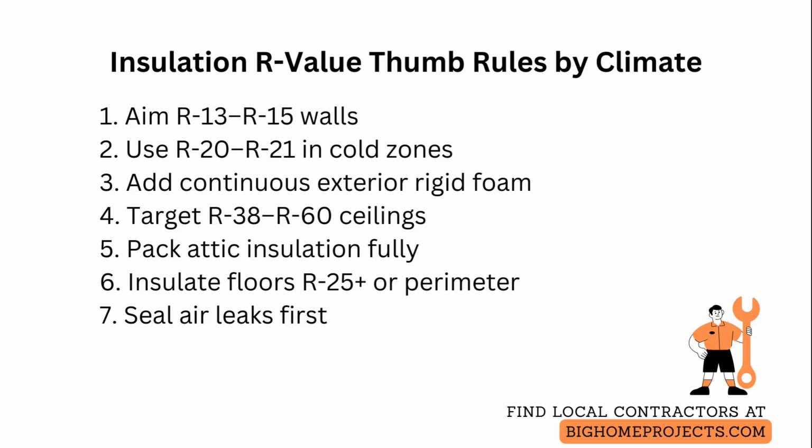prevent moisture issues. For floors above unconditioned crawl spaces, aim for R25 or higher by insulating the floor joists or, when feasible, insulating the crawl space perimeter and sealing vents to keep ducts and piping inside the thermal envelope.